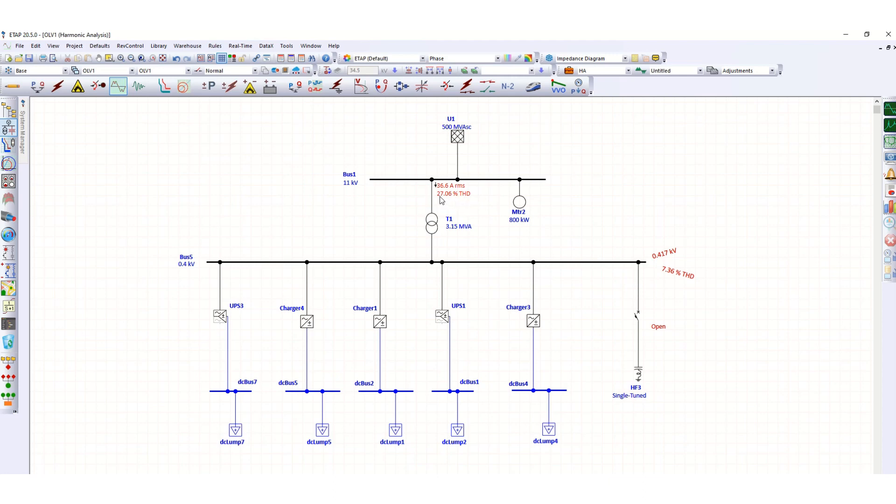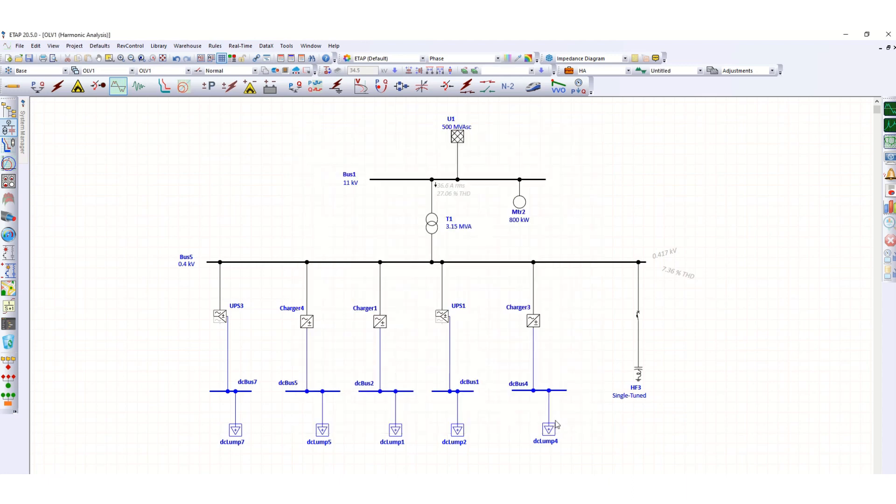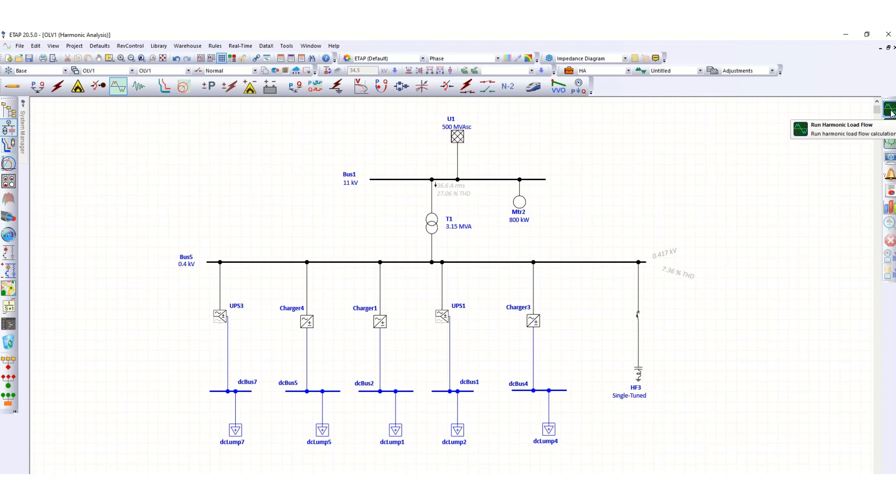Now let's recall that this THD value here is 2.06 percent and here 7.36 percent. Now what we will do, we will close the breaker here, so just close and run this. So here it was 7.36 percent and here 27 percent. Now run including this filter, now run again harmonic load flow.